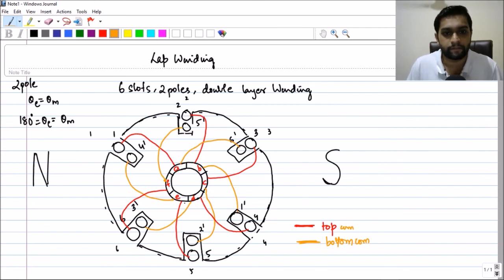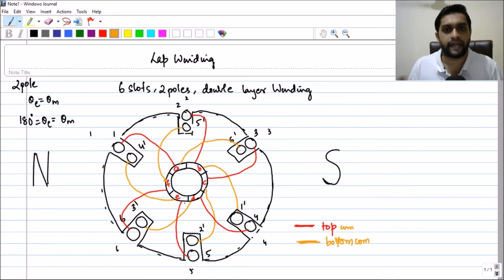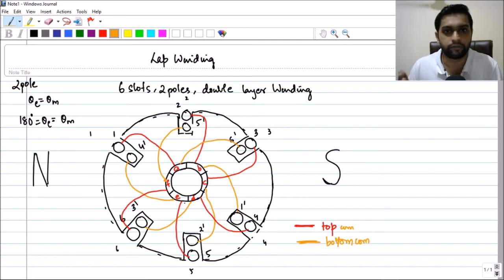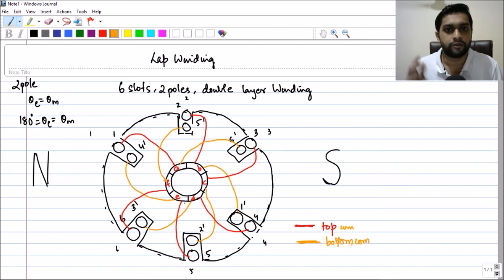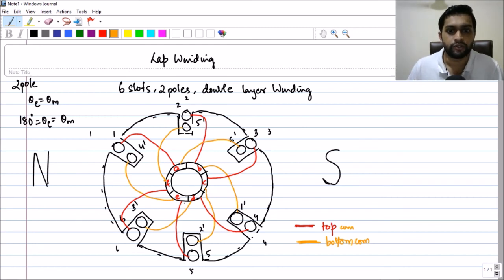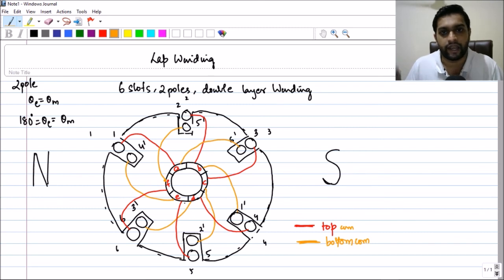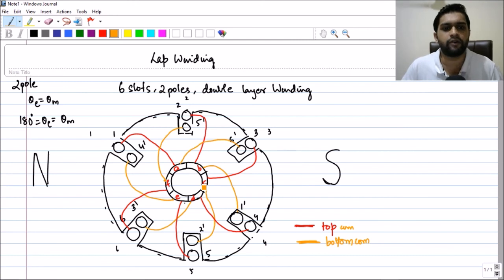So how many coils did we have? Six coils — coil one had conductors one and one-dash. In a lap winding, the end of one coil gets connected to the top of the next coil in the next slot. One-dash connects to two through commutator B; two connects to two-dash as a coil; and two-dash and three connect through commutator C. This is how a lap winding is wound.